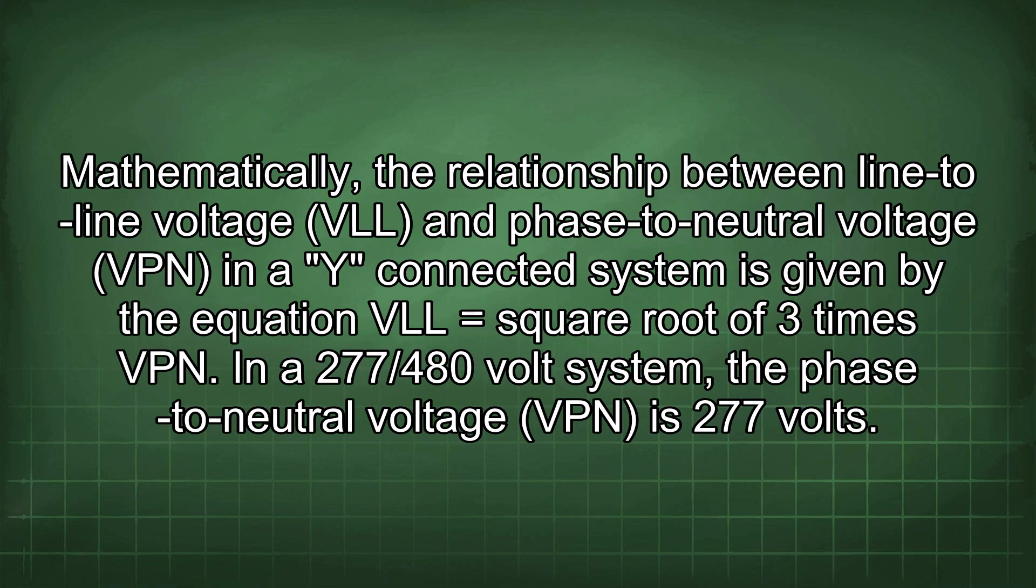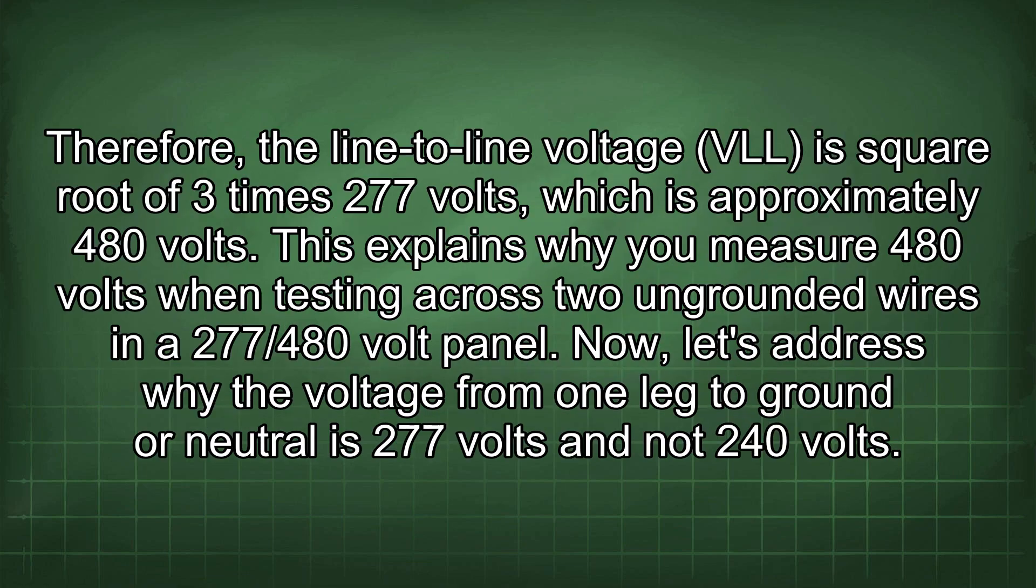Mathematically, the relationship between line-to-line voltage VLL and phase-to-neutral voltage VPN in a Y-connected system is given by the equation VLL = √3 × VPN. In a 277/480 volt system, the phase-to-neutral voltage VPN is 277 volts. Therefore, the line-to-line voltage VLL is √3 × 277 volts, which is approximately 480 volts.